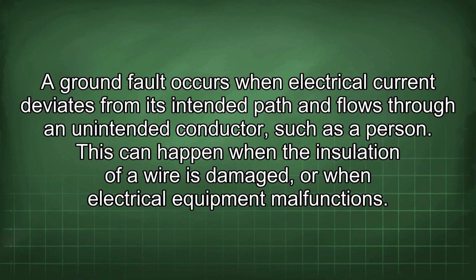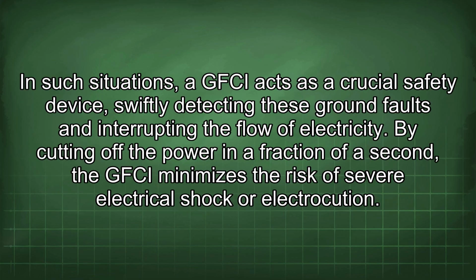A ground fault occurs when electrical current deviates from its intended path and flows through an unintended conductor, such as a person. This can happen when the insulation of a wire is damaged, or when electrical equipment malfunctions. In such situations, a GFCI acts as a crucial safety device, swiftly detecting these ground faults and interrupting the flow of electricity.